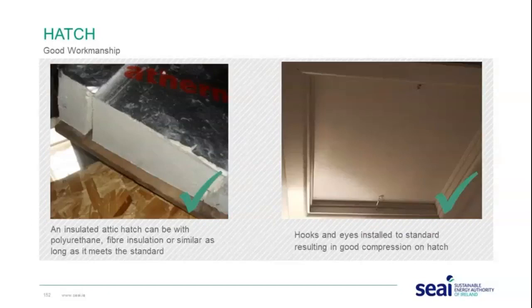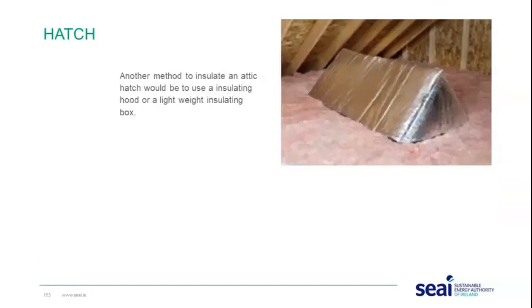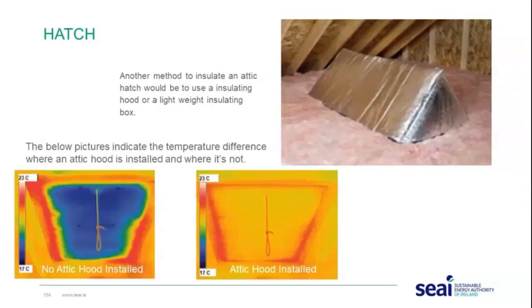Other methods to insulate attic hatches include using an insulating hood or lightweight insulating box. Thermal images show a significant temperature difference where an attic hood is not installed versus where it is installed — without the hood, the heat loss through the hatch is clearly visible. Where the hood is installed, the temperature matches the rest of the ceiling, indicating it is well insulated.